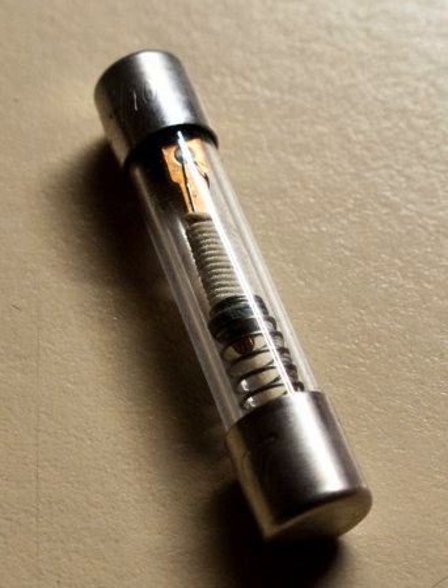Modern consumer units usually contain miniature circuit breakers (MCBs) instead of fuses, though cartridge fuses are sometimes still used, as in some applications MCBs are prone to nuisance tripping. Renewable fuses, rewirable or cartridge, allow user replacement, but this can be hazardous as it is easy to put a higher rated or double fuse element, link or wire, into the holder, overfusing, or simply fitting it with copper wire or even a totally different type of conducting object, coins, hairpins, paper clips, nails, etc., to the existing carrier.